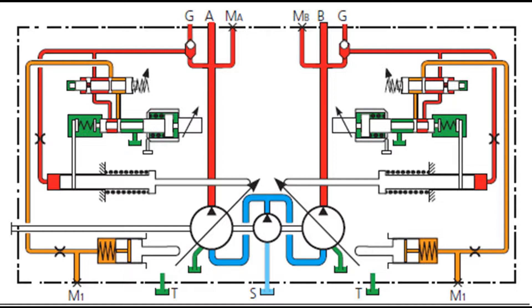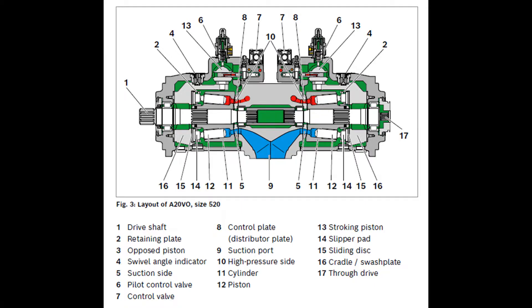LRH 1-5 Hydraulic Stroke Limiter, negative characteristic. Control from VG-max to VG-min. With increasing pilot pressure, the pump swivels to a smaller displacement. Start of control at VG-max can be set from 4 to 10 bar. State start of control in clear text in the order. Starting position without control signal: pilot pressure — VG-max, characteristic H1. Increase in pilot pressure: VG-max to VG-min, P equals 25 bar.